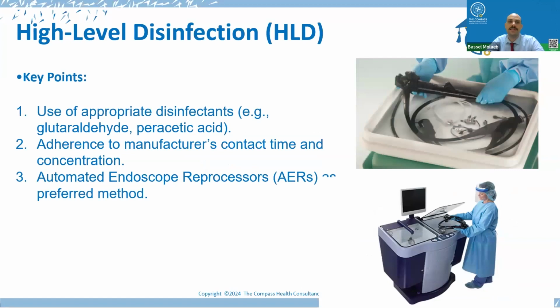So the next step would be the high-level disinfection. It is achieved either manually or through the automated endoscope reprocessor. So AERs provide a superior cleaning and decontamination, improving the rinsing of disinfectants and reducing residual disinfectants in the endoscope as compared to the manual process. High-level disinfection is the recognized minimal standard for semi-critical flexible endoscopes according to the Spalding classification.